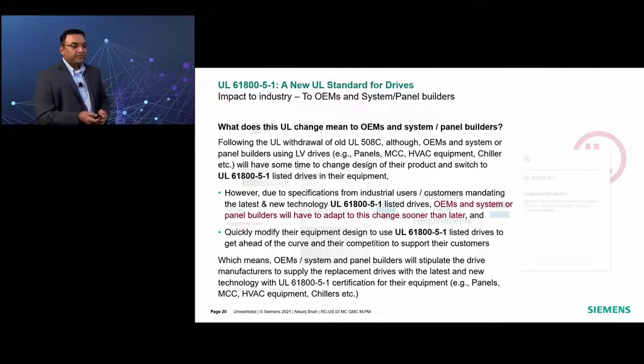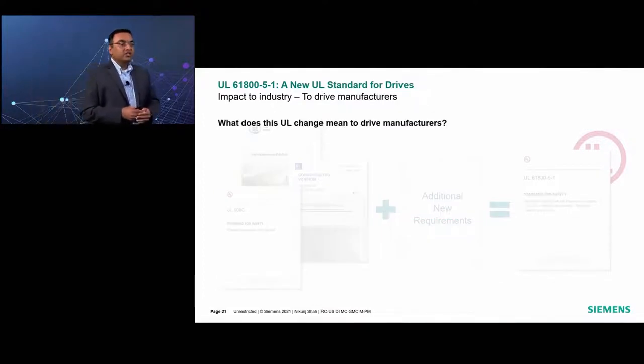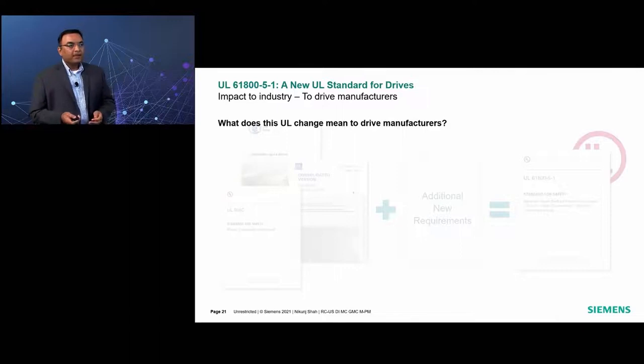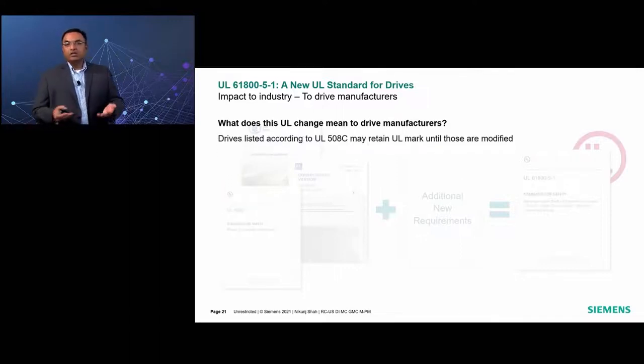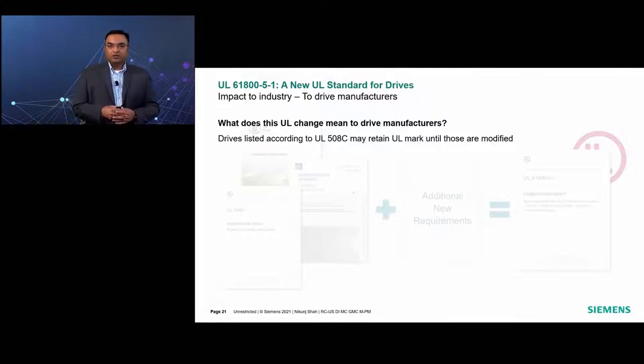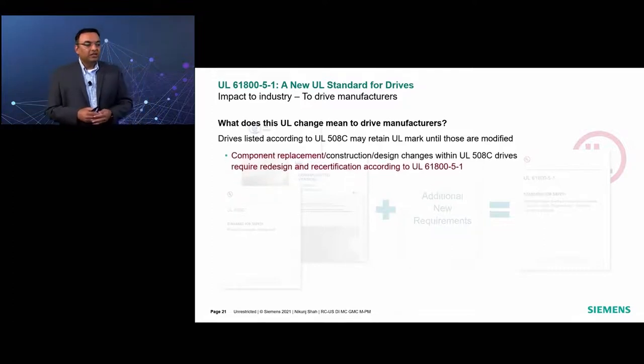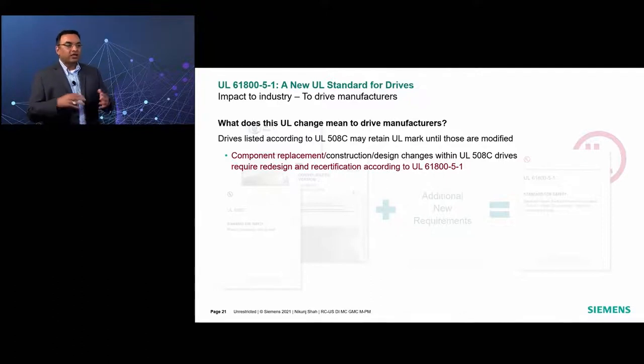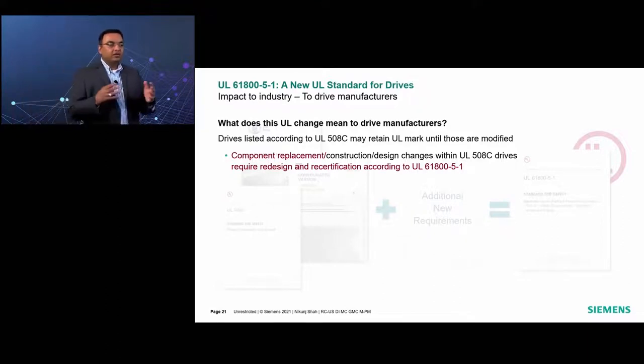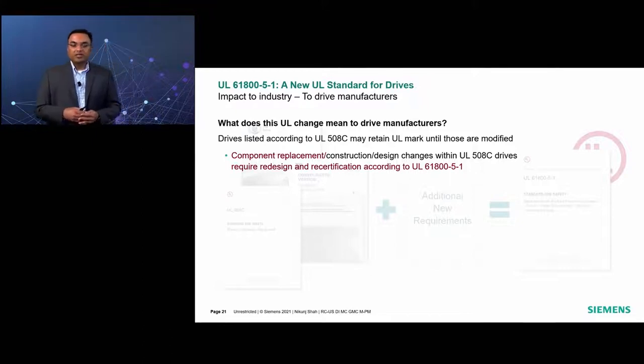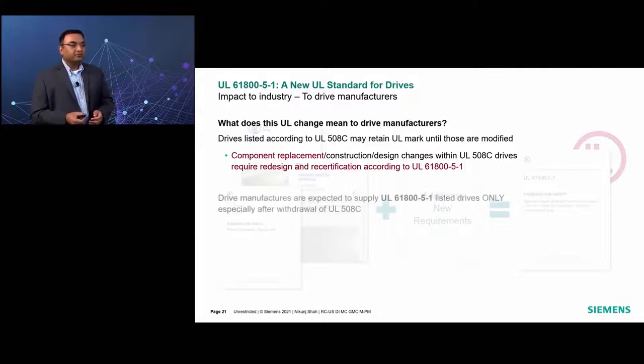Now let us see what this change means to you if you are a drive manufacturer. As I mentioned earlier, the drives listed according to the old and withdrawn UL 508C may retain the UL mark until those are modified. What does this mean? It means that if a component replacement is required within that existing 508C listed drive, or any design or construction changes are required, then those drives have to be completely redesigned and recertified according to UL 61800-5-1 based on this new latest technology requirement.